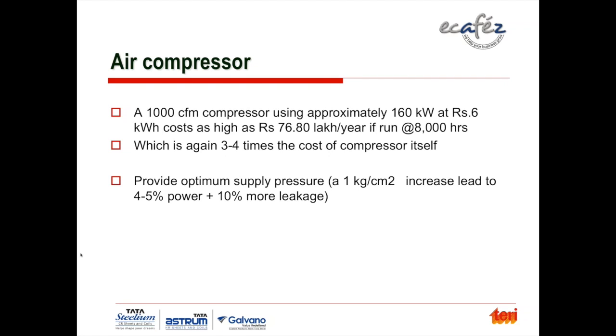One of the most important is to operate the air compressor at the right pressure, because a 1 bar increase in the air compressor pressure increases the power consumption by 4 to 5%. Not only does it increase the power consumption, it also increases air leakages in the plant by 10% or so. So the first thing is to check at what pressure you are operating the compressor and what pressure you are using the air at, and try to match that, maybe half a bar more or 1 bar more, not more than that.